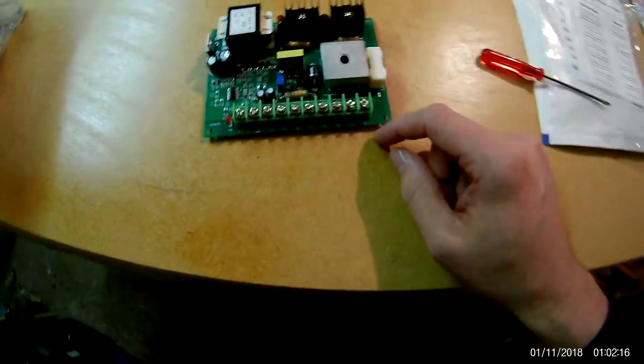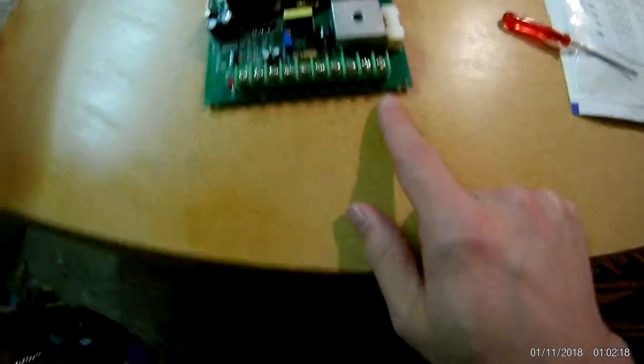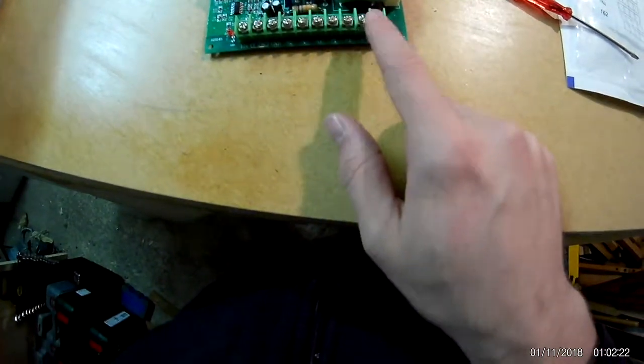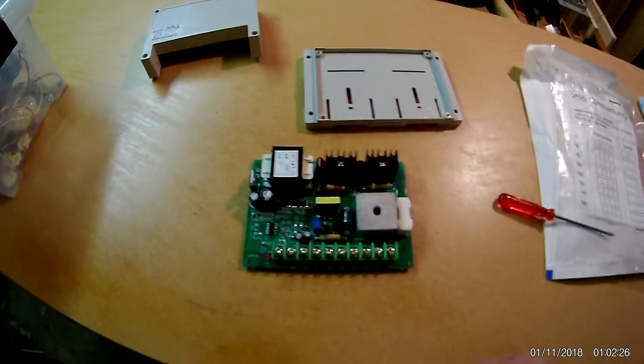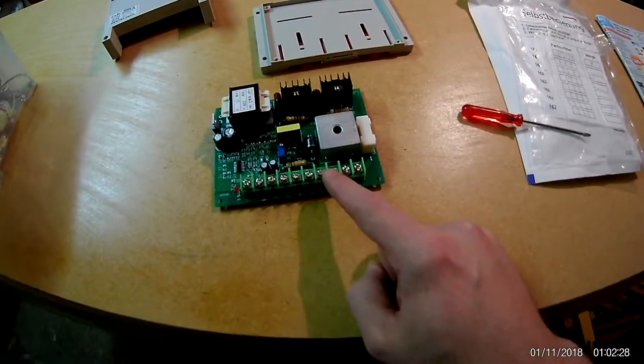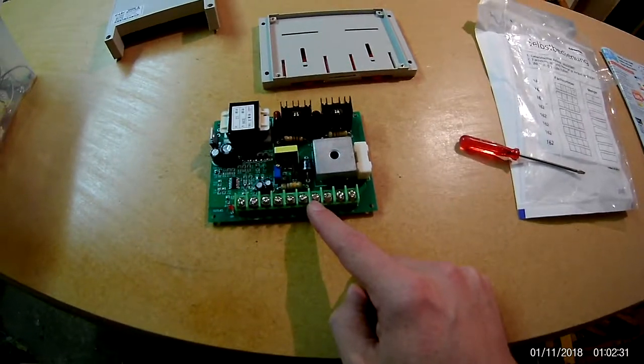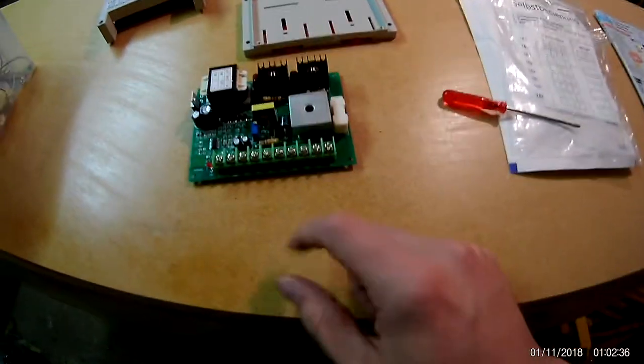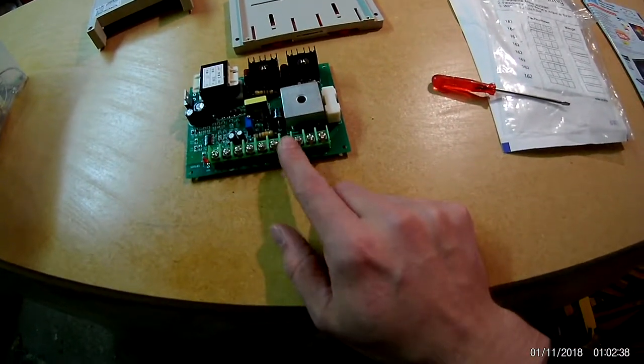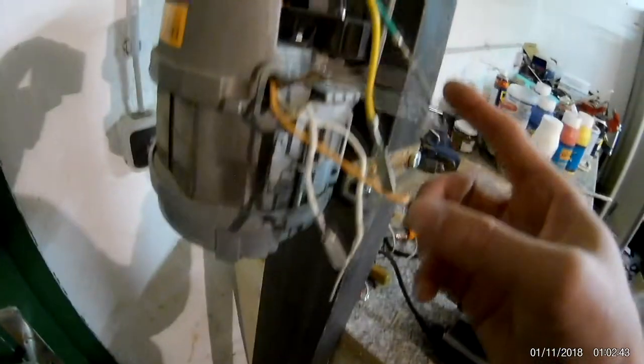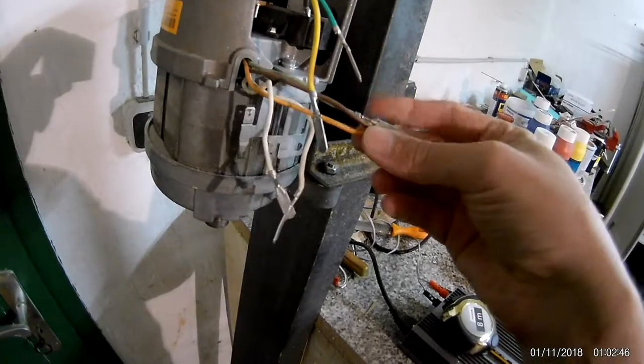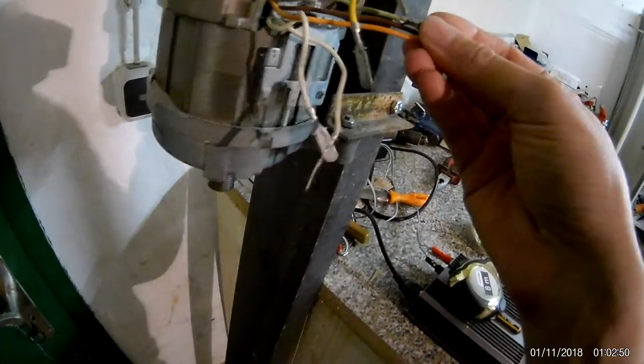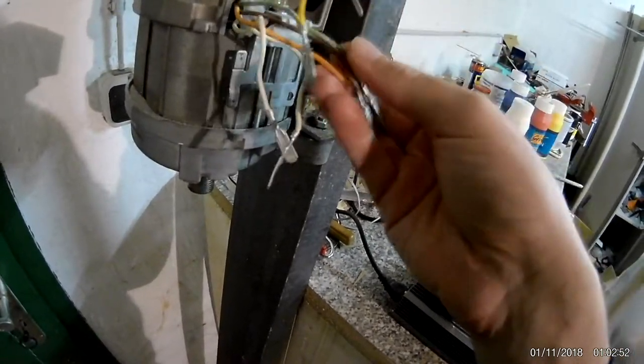Let's look at the inputs. L N - line neutral, that's 230 volts, or 220. It says 220, I think we have 230 here. F1 F2, according to the manual which was in Chinese and I had to translate using Google Translate app, it says excitation coil. In our case that would be orange and brown or green - these three wires are the excitation coils. The problem is our excitation coil has one ohm of resistance.